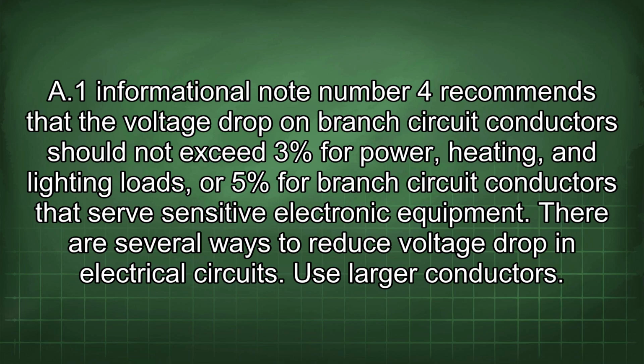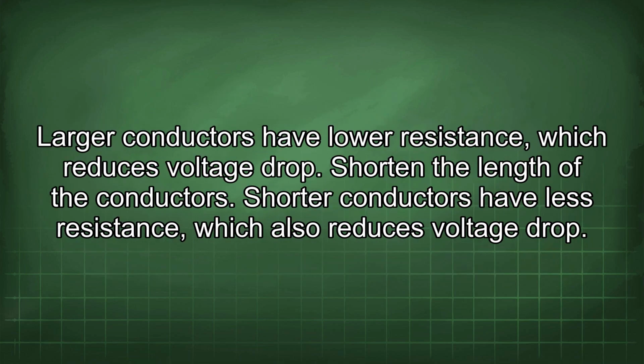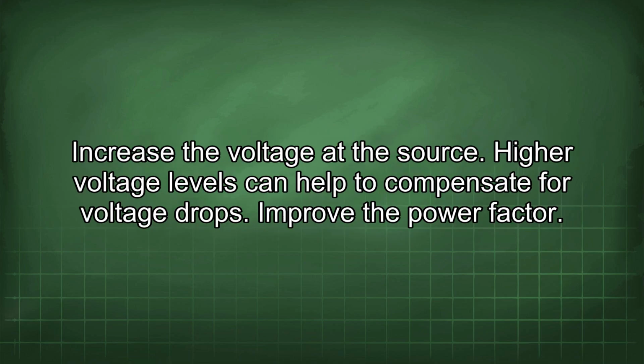There are several ways to reduce voltage drop in electrical circuits. Use larger conductors. Larger conductors have lower resistance, which reduces voltage drop. Shorten the length of the conductors. Shorter conductors have less resistance, which also reduces voltage drop. Increase the voltage at the source. Higher voltage levels can help to compensate for voltage drops.